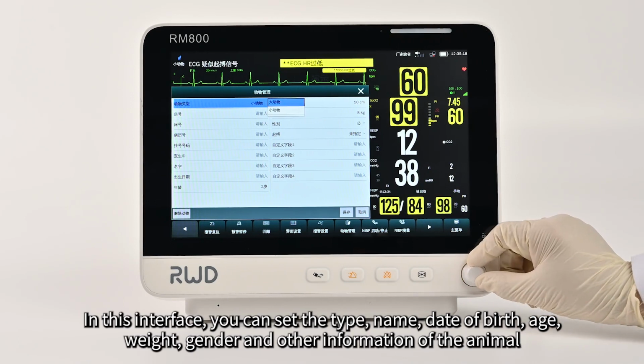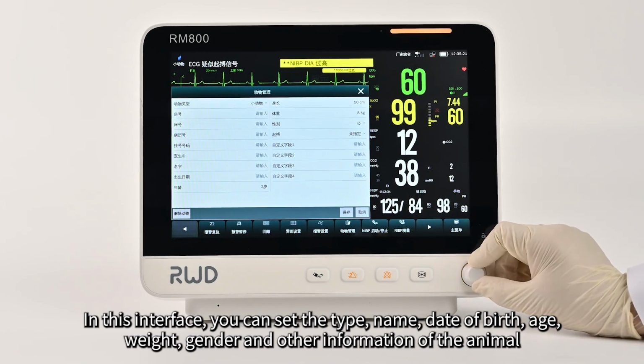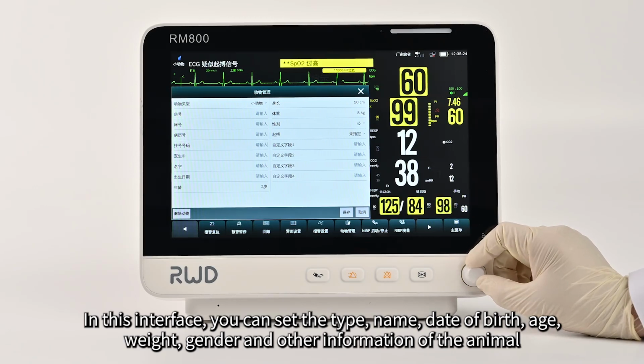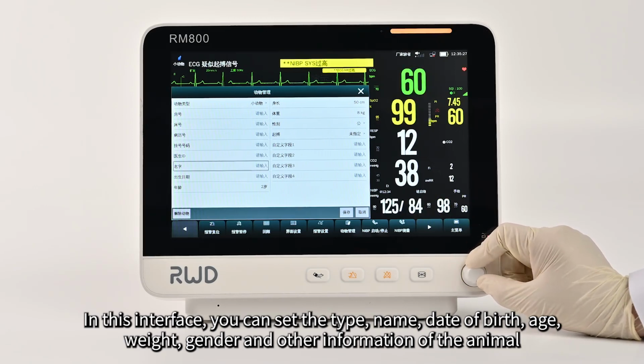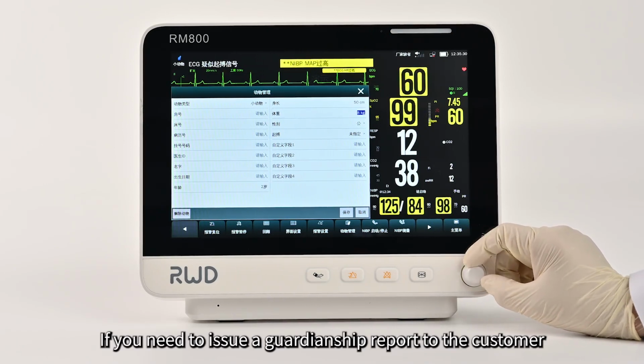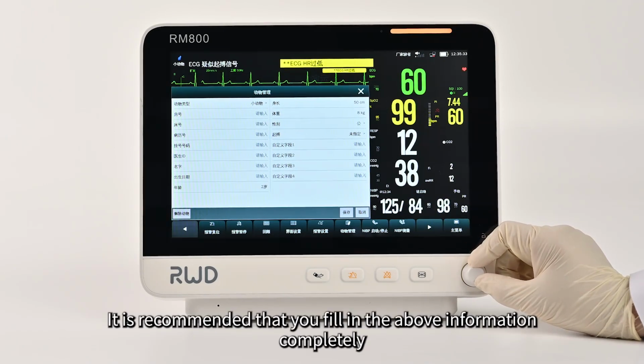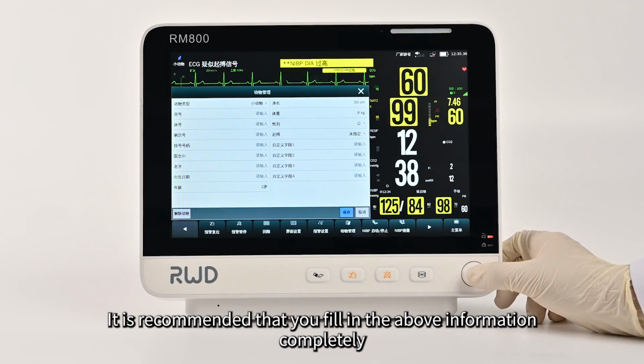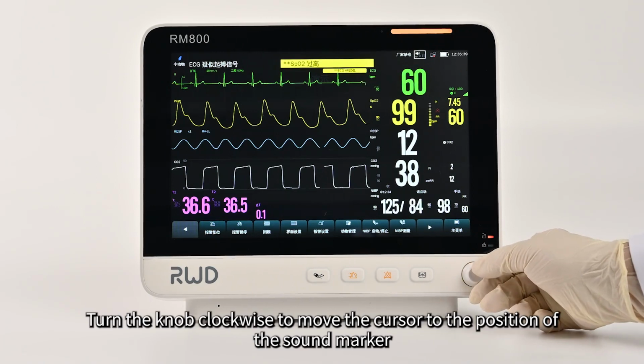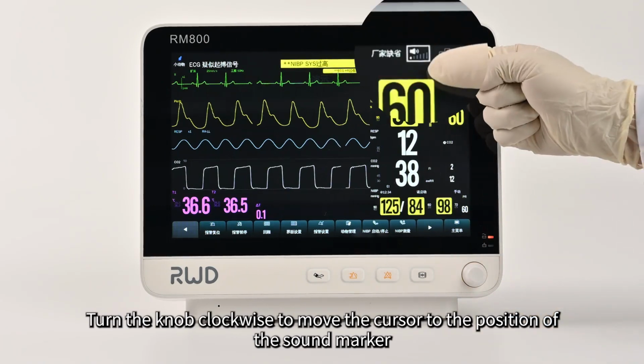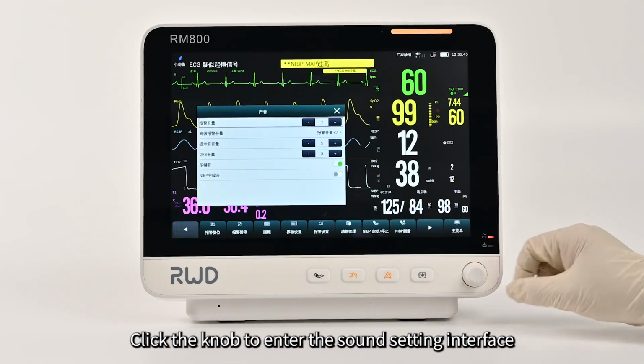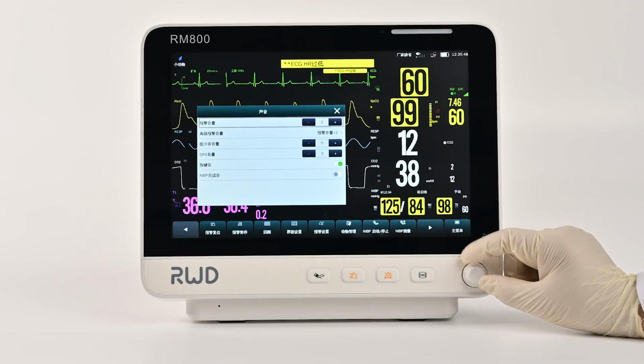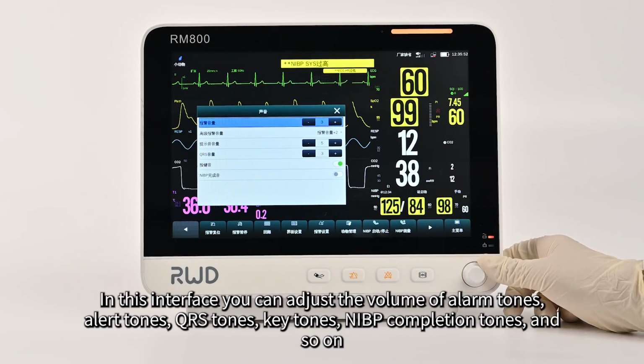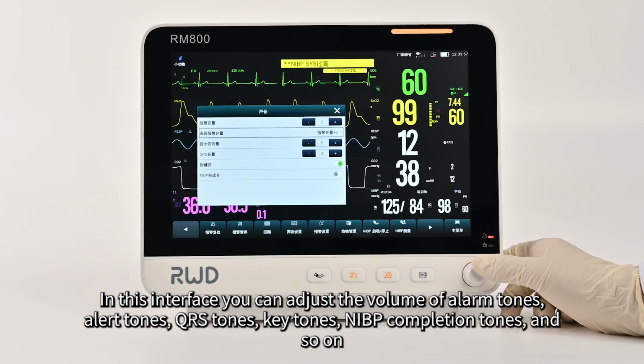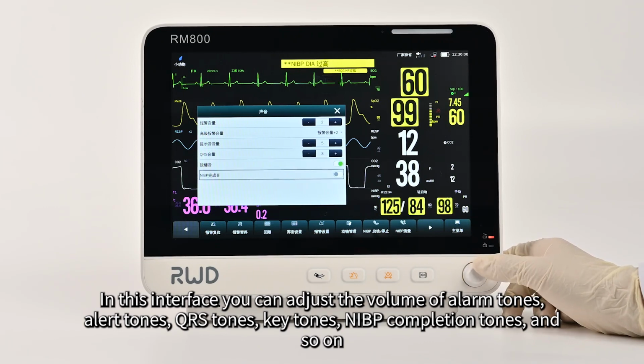In this interface, you can set the type, name, date of birth, age, weight, gender and other information of the animal. If you need to issue a monitoring report to the customer, it is recommended that you fill in the information completely. Turn the knob clockwise to move the cursor to the sound icon. Click the knob to enter the sound setting interface. In this interface, you can adjust the volume of alarm tones, alert tones, QRS tones, key tones, NIBP completion tones, and so on.